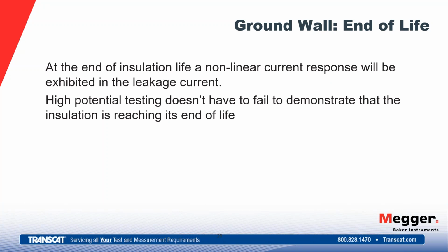Finally, here we bring ourselves to a higher voltage test. This is our indication of end of life if we're failing our ground wall tests here. At the end of insulation life, a nonlinear current response exhibits itself in the leakage current. So high pot testing does not have to fail to demonstrate that insulation is reaching its end of life.